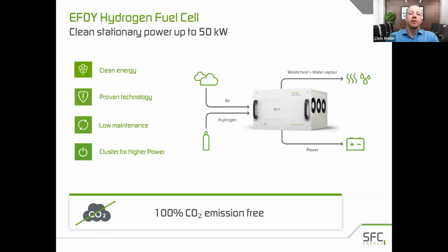Moving on to SFC: back in 2020, SFC Energy acquired the rights to an existing hydrogen fuel cell technology and has since worked to improve the design and secure the necessary certifications to bring this technology to new markets like North America. With an install base of over 1,000 units in Europe, our field-proven hydrogen fuel cell technology provides zero-emission clean energy in 2.5 kilowatt modules that can be paralleled together up to 50 kilowatts.